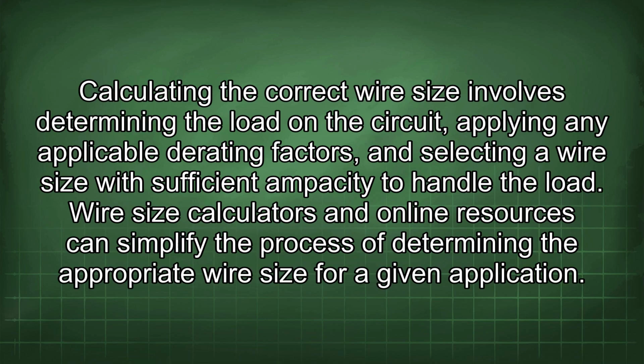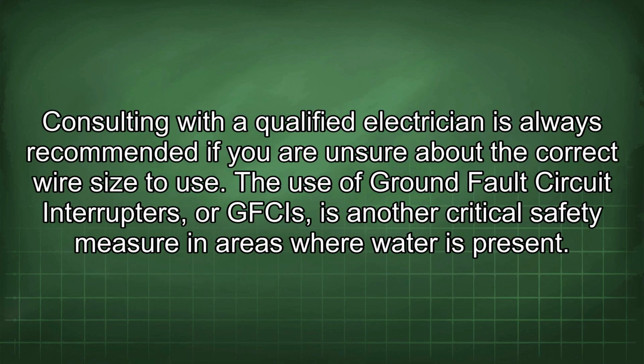Calculating the correct wire size involves determining the load in the circuit, applying any applicable derating factors, and selecting a wire size with sufficient ampacity to handle the load. Wire size calculators and online resources can simplify the process of determining the appropriate wire size for a given application. Consulting with a qualified electrician is always recommended if you are unsure about the correct wire size to use.